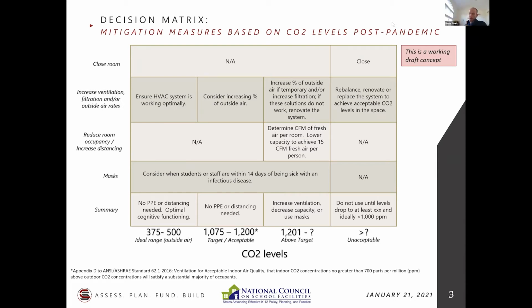Got it. And this goes back to what I was saying, a snapshot in time. If you walked into a classroom and you got 2,500 parts per million, bam, hey, you're not doing your job. Walk in there otherwise, and you get some lower values. You want a data set, maybe throughout a week, 2 weeks, and you're analyzing, is it consistent? Do you have multi-zone operation? Do the other classrooms that are tied into the classroom you're looking at have similar occupancy? In a perfect world, that'd be great. Then you could rely on those values more.